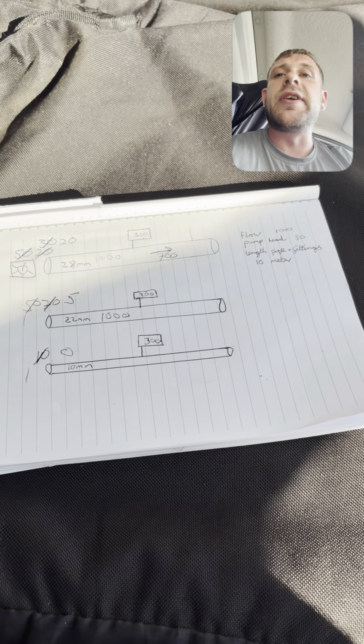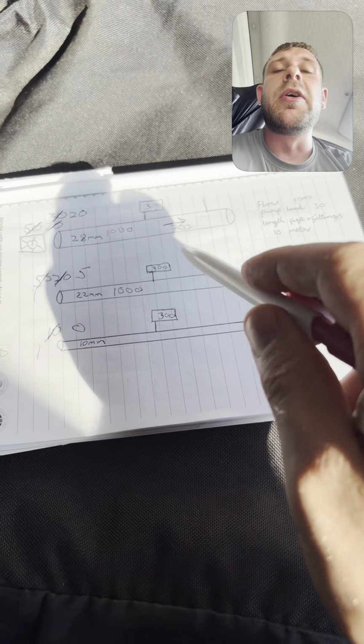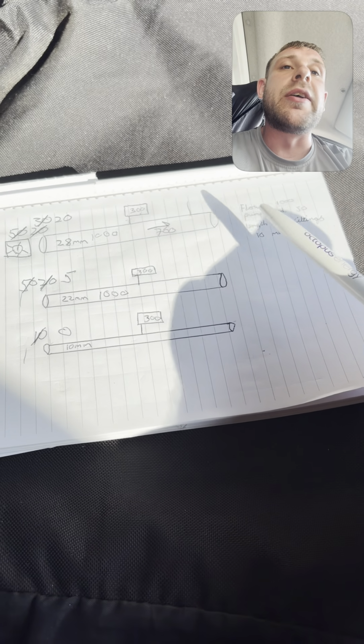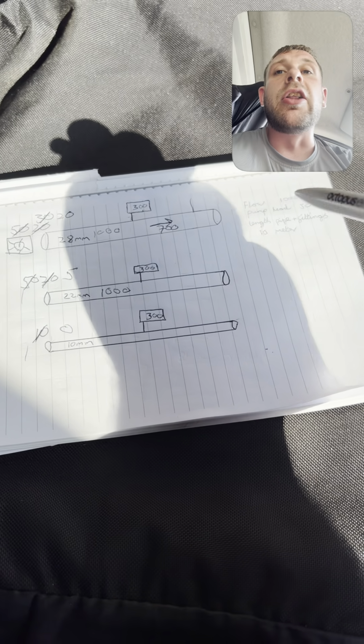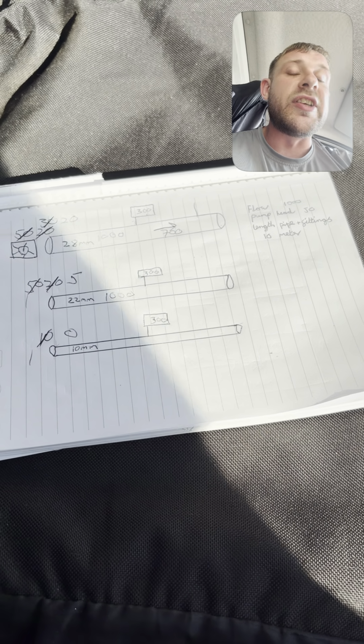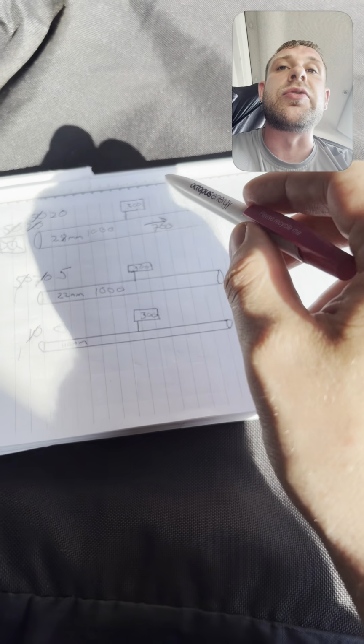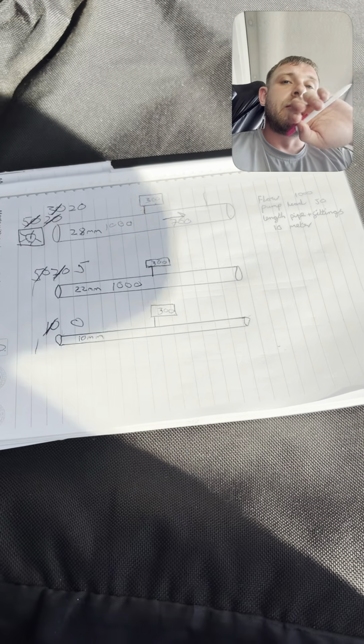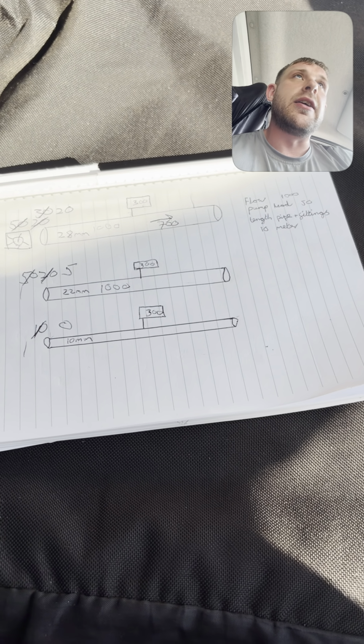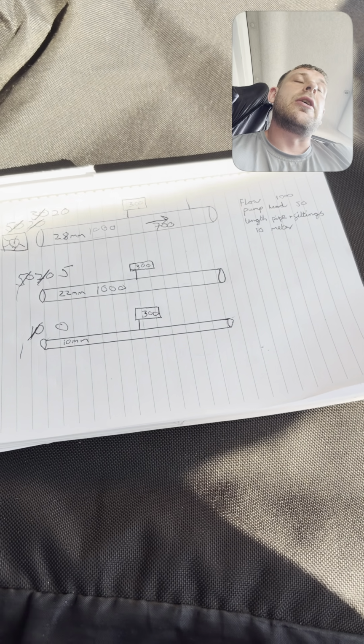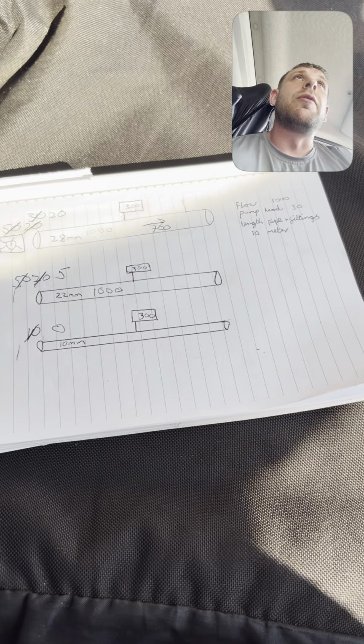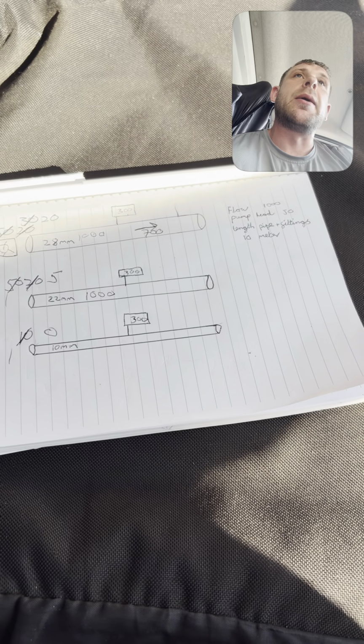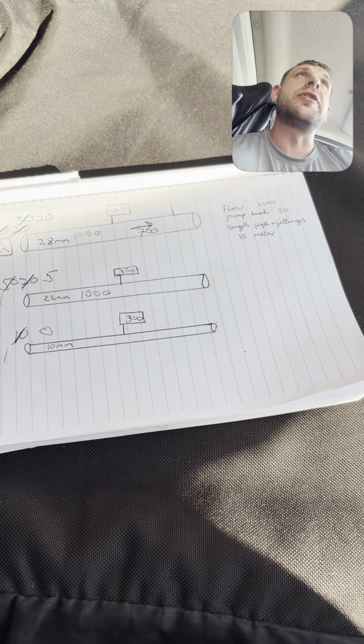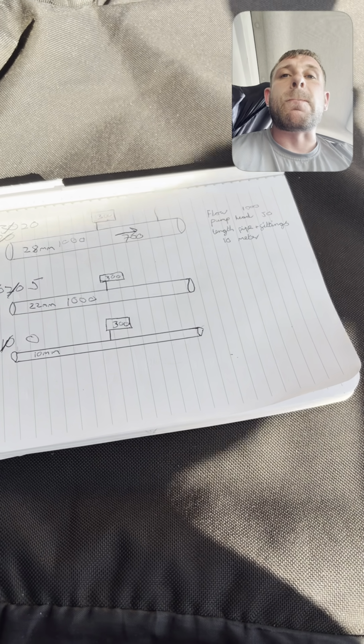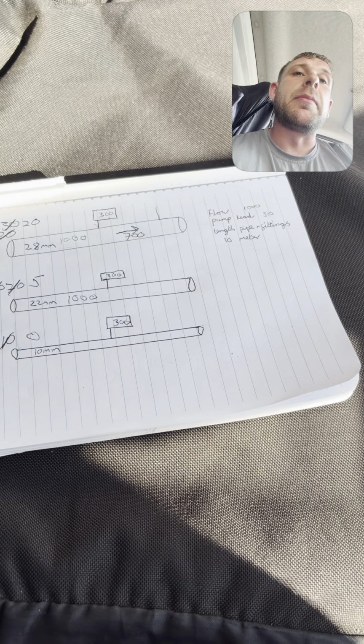Another way around things is, you've got to think, the reason this wasn't so important with boilers was because boilers run at a lot lower flow rates. So you didn't really get this situation so much. On a heat pump it's carrying 1,000 litres per hour, whereas on a boiler it could have been 250 litres per hour, so it runs about 4 times faster on a heat pump. So if you imagine you've got pipework running at 1,000 litres per hour, the smaller that pipework goes, the more resistance you're going to get, the more pressure loss you're going to get, and the more pump head you're going to lose. But with boilers we didn't really have that problem as much.